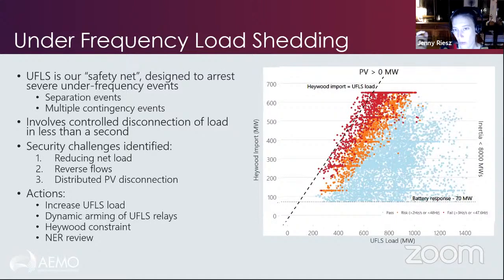It will still trip when we hit a severe under-frequency, and it will actually be exacerbating the disturbance rather than helping to correct it. To make matters even worse, we believe that very large amounts of PV will start to trip themselves based on their own internal protection in the inverter when frequency starts to drop below about 49 hertz. And that means that if we hit 49 hertz, which is where our under-frequency load shedding begins, that trip of PV will also exacerbate the disturbance and make it much harder to arrest that frequency decline.